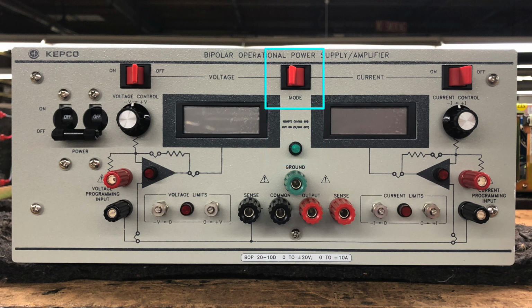As for the controls, in the center is the voltage mode current mode switch. On either side of that switch are the voltage control and current control switches. These switches, along with their respective knobs, allow setting the desired output voltage or current. Next to the output terminals are the voltage limit and current limit potentiometers, which allow setting negative and positive limits for both. These limits are active regardless of the unit's mode of operation.